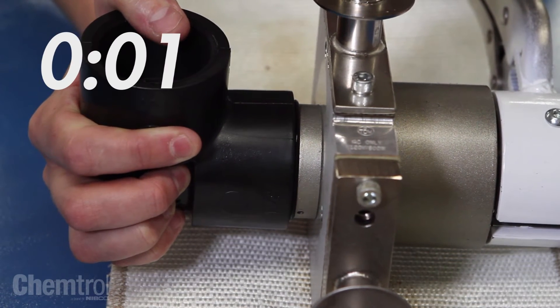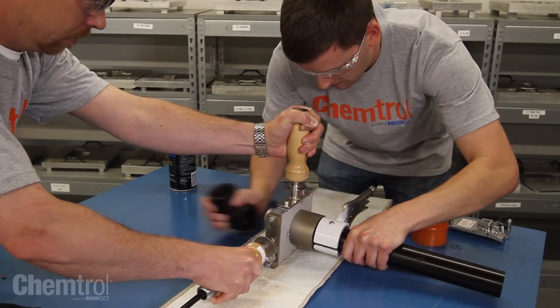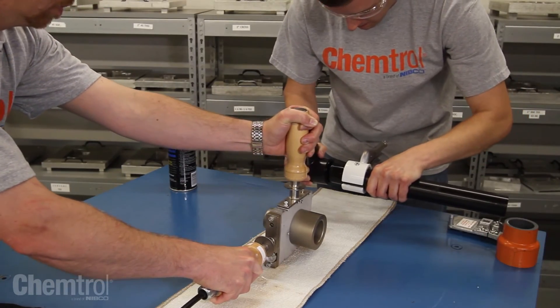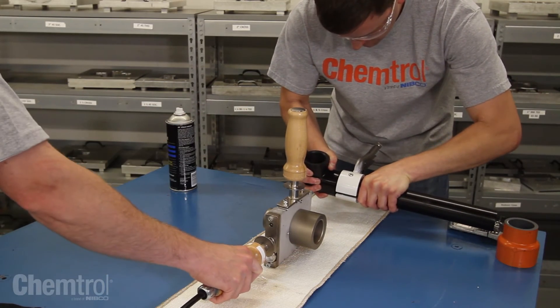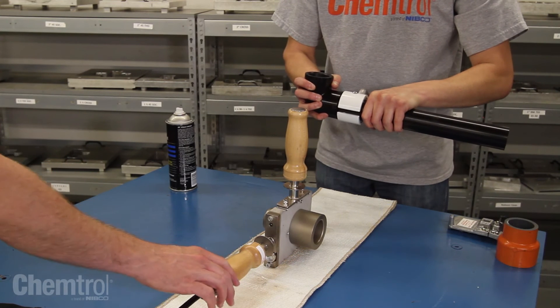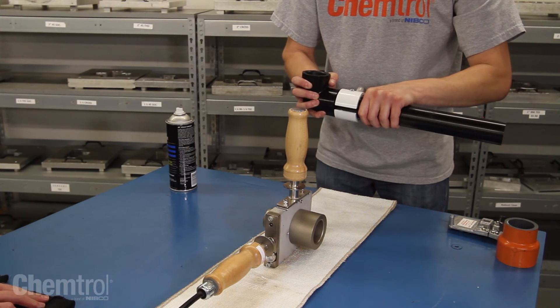When the timer beeps, simultaneously remove the pipe and fitting and immediately insert the pipe squarely and fully into the socket without purposeful rotation. Hold steady for 30 seconds, allowing the fusion joint to set up.